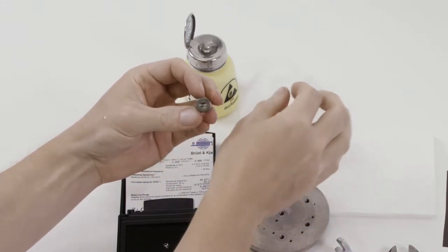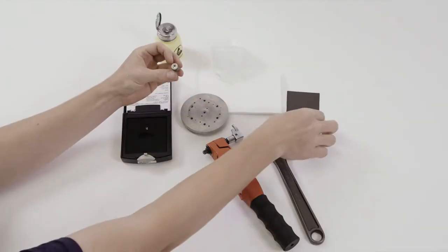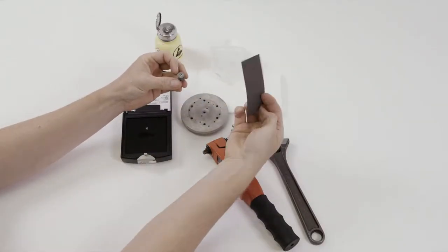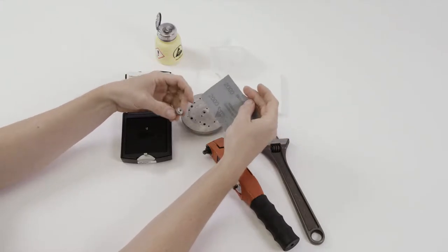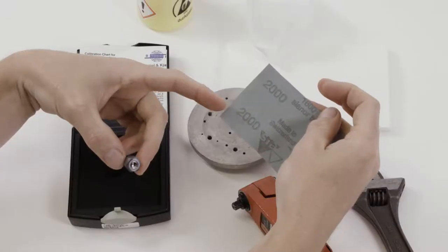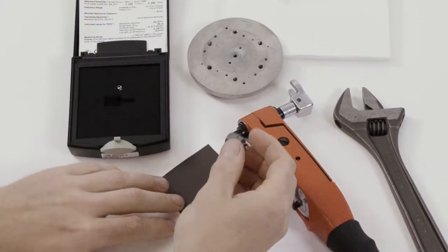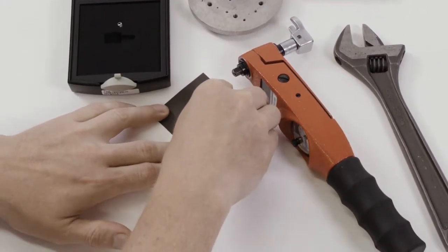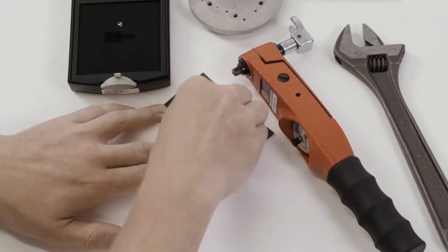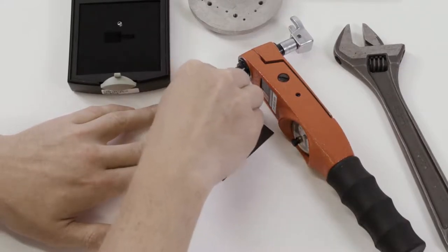In case minor damage has incurred on the mounting surface, the use of a fine sanding paper, grade 2000 for example, is recommended. When lapping a surface for preparation to mounting, move the accelerometer in figure eight circles.